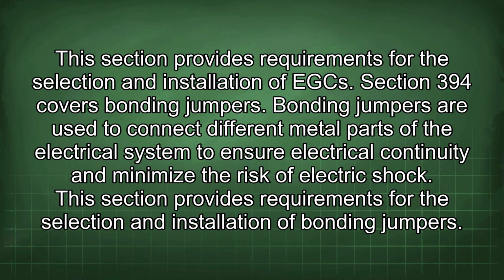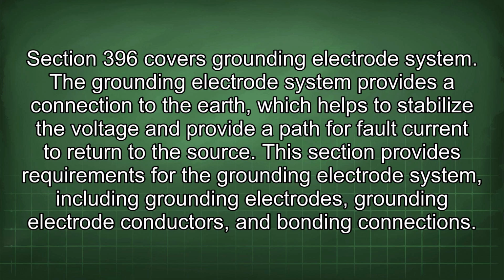Section 394 covers bonding jumpers. Bonding jumpers are used to connect different metal parts of the electrical system to ensure electrical continuity and minimize the risk of electric shock. This section provides requirements for the selection and installation of bonding jumpers. Section 396 covers grounding electrode system. The grounding electrode system provides a connection to the earth, which helps to stabilize the voltage and provide a path for fault current to return to the source. This section provides requirements for the grounding electrode system, including grounding electrodes, grounding electrode conductors, and bonding connections.